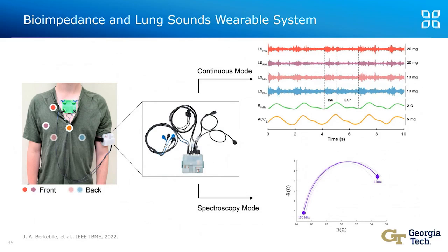And we had worked on this device that we have now tested in about 10 or 15 patients who were hospitalized at Grady in the emergency department. And we've recorded measurements from them of lung sounds from various places on the chest and back, as well as impedance pneumography through a single device that then allows these basically to be recorded in a way that both signals can be analyzed in the context of each other.